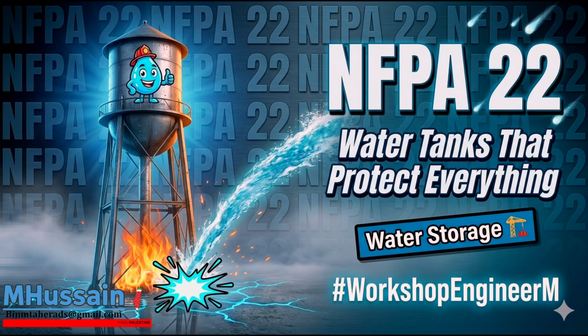It's a fair question, but the water only protects the thin steel shell of the tank itself. It does absolutely nothing to protect the structural steel tower supporting that tank 100 feet in the air. We are dealing with massive, exposed steel columns. And to understand why this is a code requirement, we have to look at the metallurgical properties of steel under thermal load. Right. Structural steel, like the common ASTM A36 used in heavy construction, has incredible yield strength at ambient temperatures.